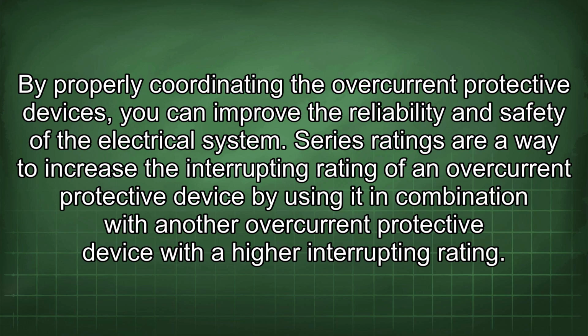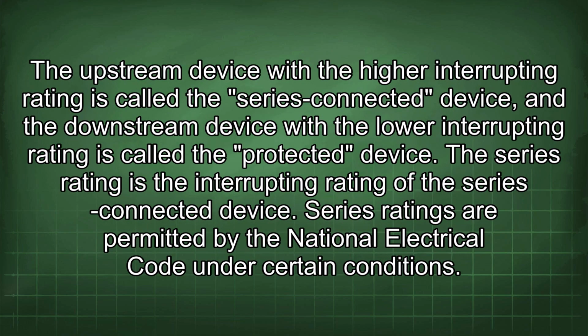Series ratings are a way to increase the interrupting rating of an overcurrent protective device by using it in combination with another overcurrent protective device with a higher interrupting rating. The upstream device with the higher interrupting rating is called the series connected device, and the downstream device with the lower interrupting rating is called the protected device. The series rating is the interrupting rating of the series connected device.